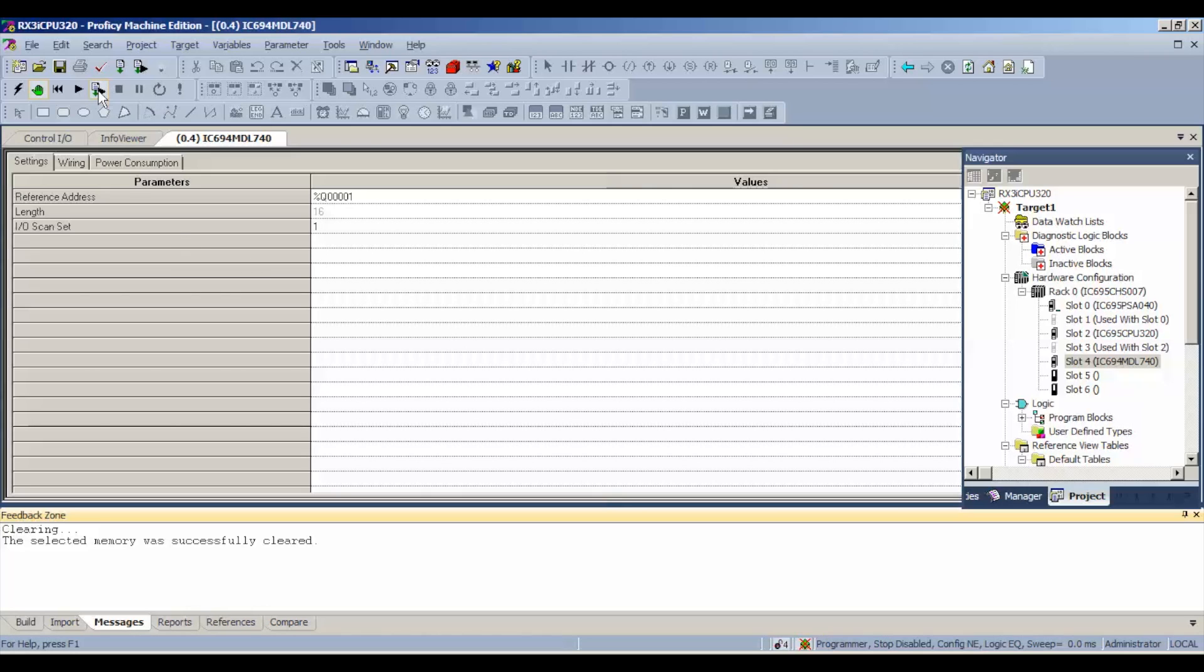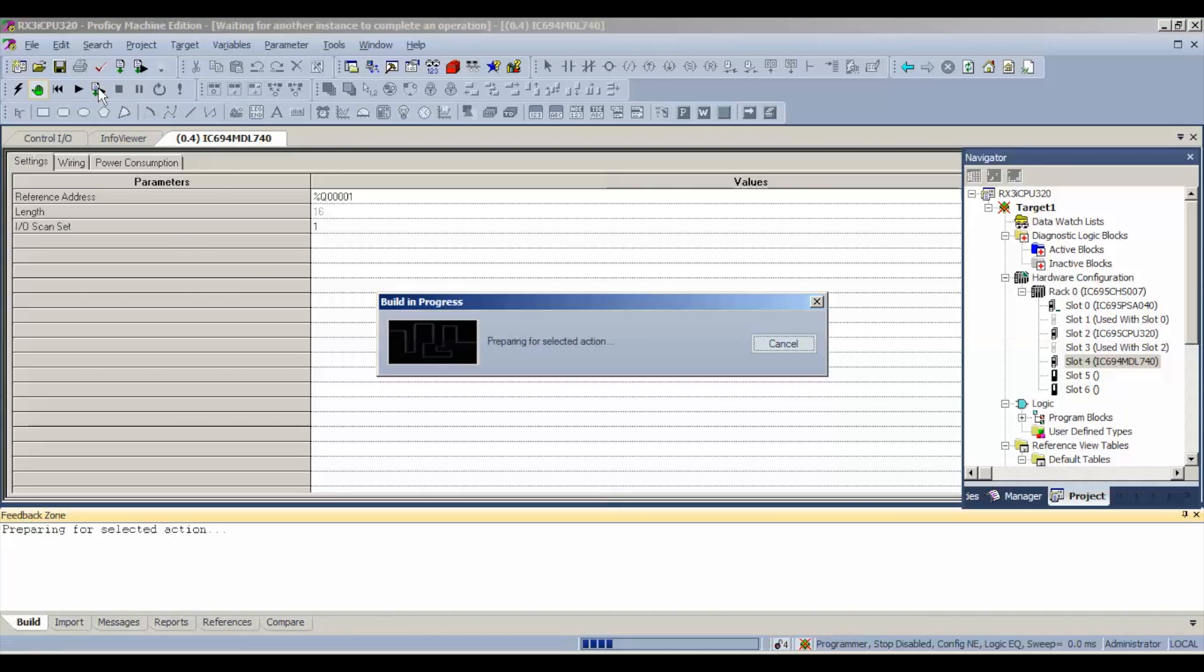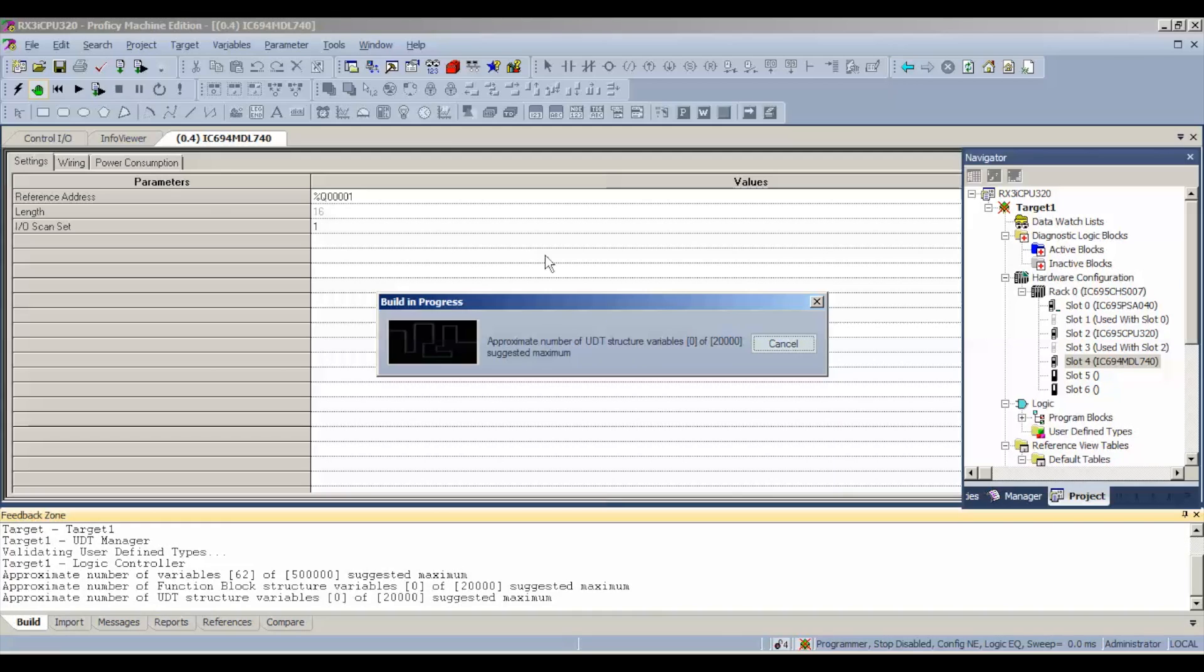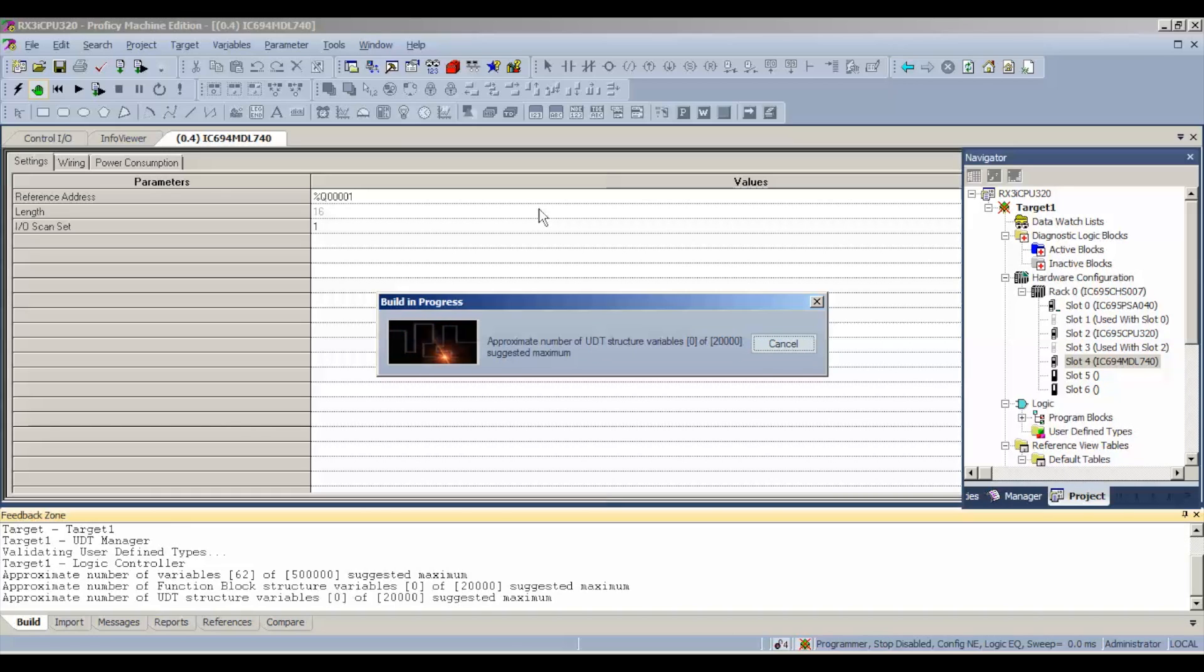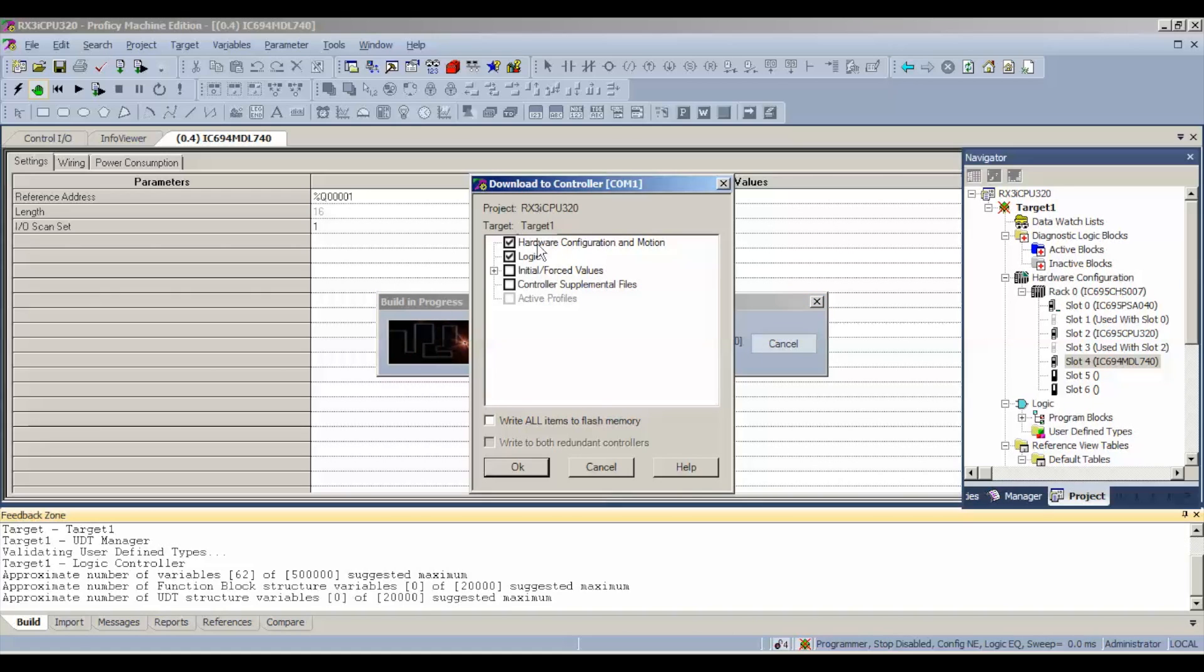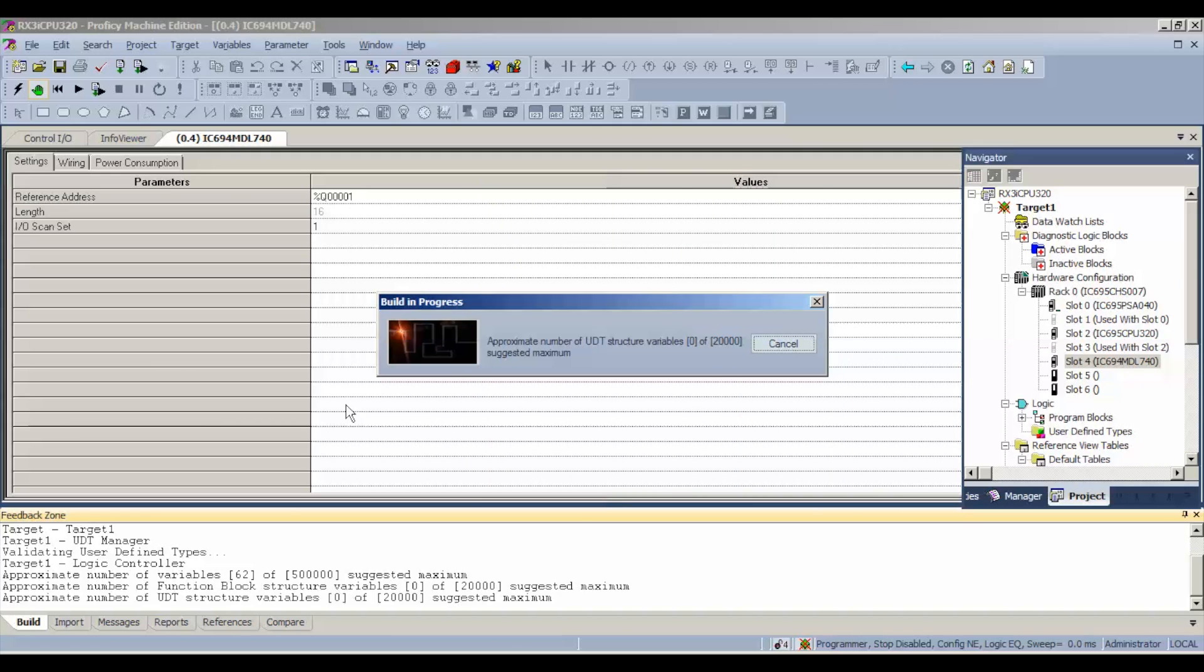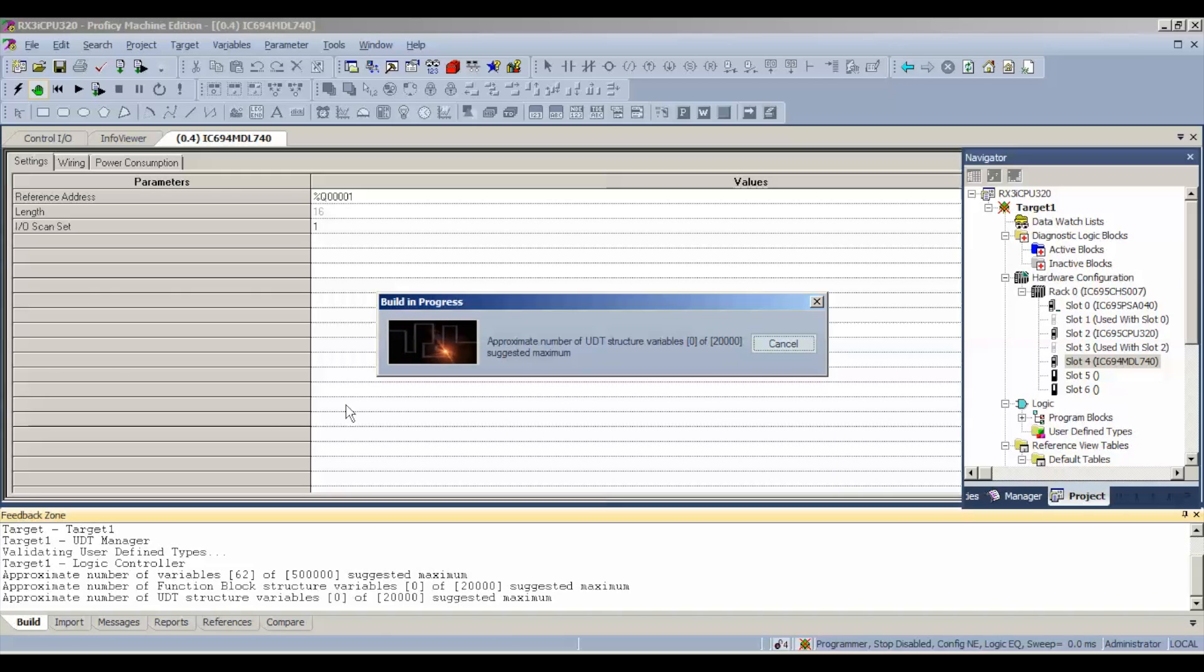So let's go to our download button, this download information icon and run button in one, download and start. Now the first thing it's going to ask us is what exactly do we want to download to the controller. In this particular case, just hardware configuration and motion and logic. Just the top two selections. This is a simple test and we're going to be toggling bits on and off. So there's no need to write that to permanent flash memory or force values or anything like that.